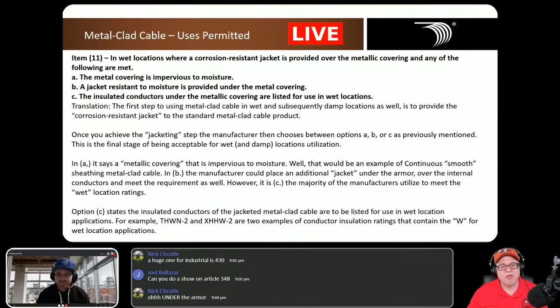Okay. So C is the one that almost all of us manufacturers use. The most commonly used product in the industry is interlocked MC. That's the most widely used product out there. And for us to get a wet location rating, we take normal MC, which is the inner conductors, wrapped with a polymeric wrap, and then the armor is placed over it, and then we extrude PVC material over the armor. So the inner conductors inside of it are wet location rated, and that would be THHN/THWN-2 or XHHW-2.